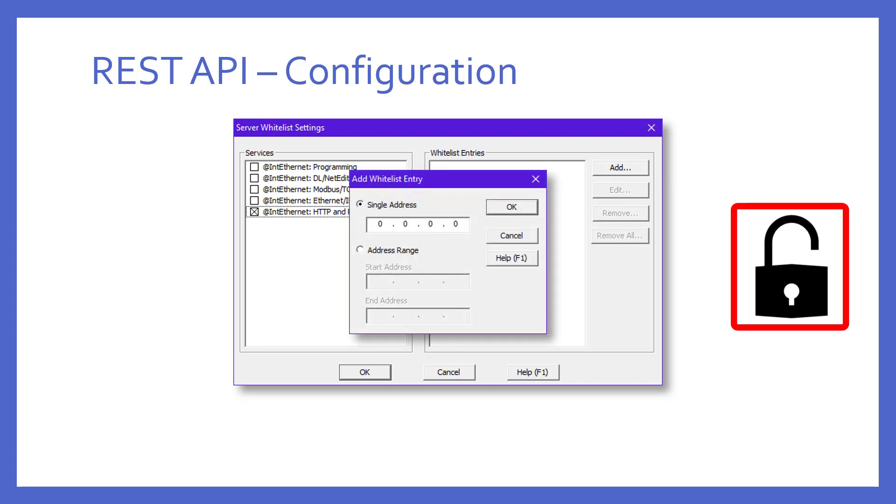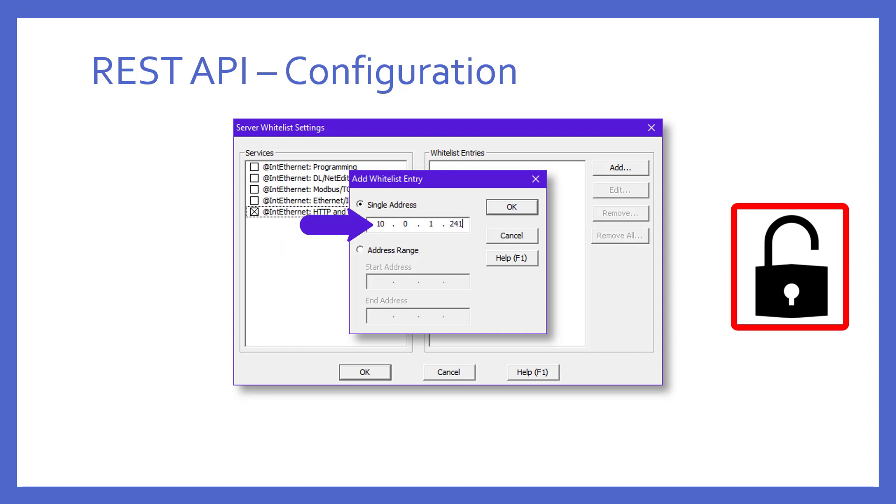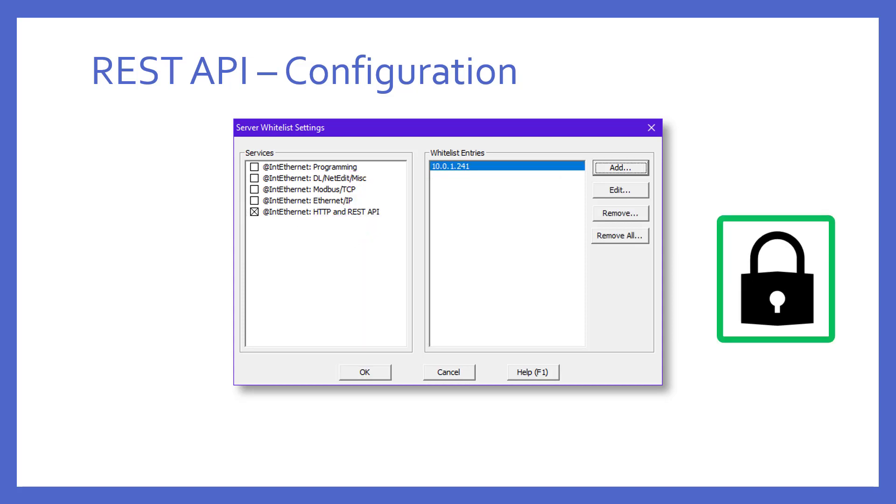With regards to HTTP and REST API, if we put an X in the box, then you'll notice the Add button at the right is enabled. Then if you press the Add button, you can add IP addresses one at a time if they're non-contiguous or IP address ranges to the whitelist. Here, I enter my PC's IP address, for example. And then I'd press the OK button. The result is this. This now means that the only IP address that can utilize the REST API is my particular PC in this case. All other IP addresses that attempt to utilize this service will be rejected.